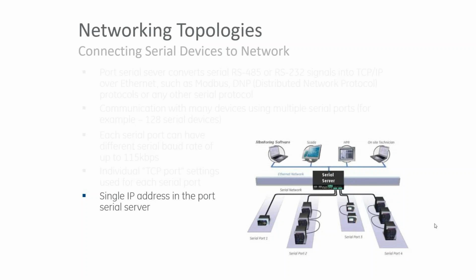The alternate to that is maybe you don't need to talk to those devices on the serial network. All you need to do is gather the information. So what you could do is set up a Modbus map or DNP map in your serial server and just access that map directly from the serial server, and then just have different locations in the address list for the different devices. But that requires more configuration and an additional device that you have to maintain with a mapping.